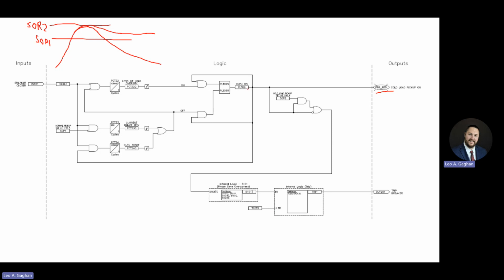And then the way that this works is, if cold load pickup is off, we would have a 0 right here. That 0 is going to go to this NOT gate, become a 1, which will allow it to pass through. And if cold load pickup is off, we'll have just our normal torque control, and we'll have our normal curve, right? We'll just have a normal curve with a pickup of 1.4.